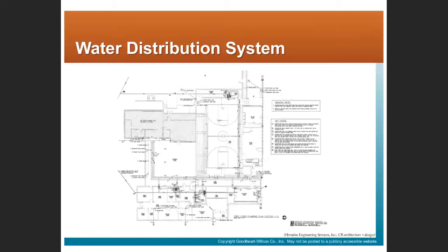HWR is something that you're going to find in commercial construction and generally not in residential construction. HWR is hot water return. So in a commercial building, you'll often have a hot water return line, which gives you a way to have that hot water moving around in a circle, such that if you're way at the end of the line and you turn on the hot water faucet, you don't have to wait 3 or 4 minutes for the hot water to get from the hot water heater way over on the other side of the building. There's some hot water moving around, then you get your hot water a little bit quicker.